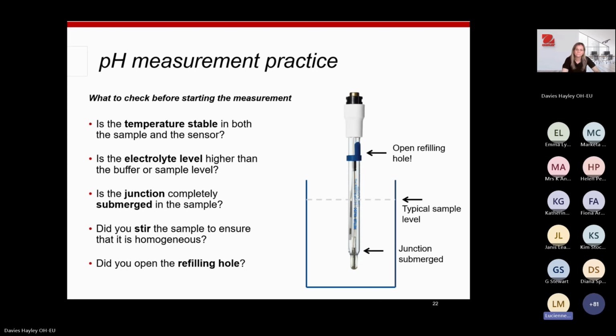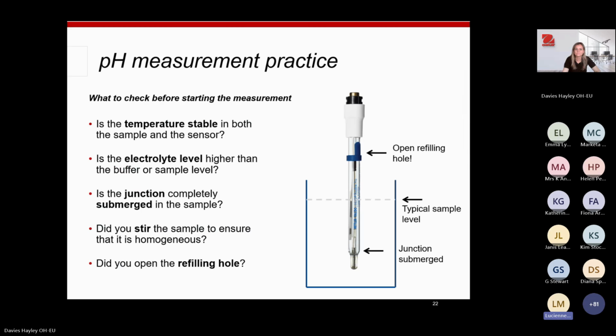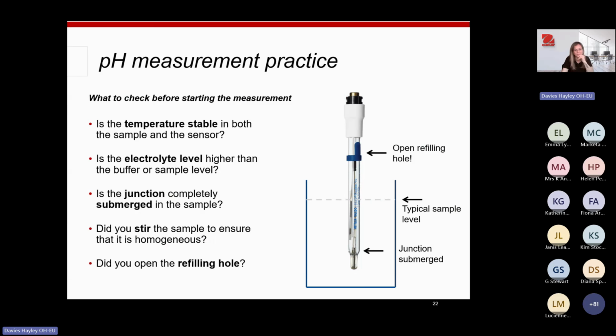Just coming back to the question around the mold. Wendy's come back and says they're stored in pH 4 buffer and are very old. Okay. So it would be a case of replacing your electrolyte storage solution, and then I'll double check which of the solutions would be best to get rid of the mold. But you could try the storage solution and soaking it in that, and then try giving them a clean. And remember, try not to rub the electrode, just dab them, so as not to cause any kind of electrostatic on the junction or the electrode.